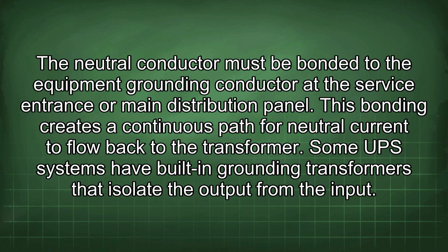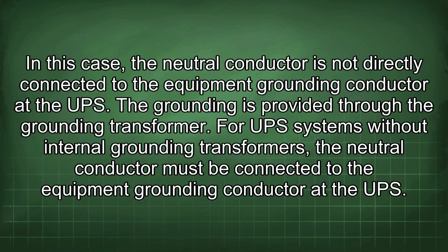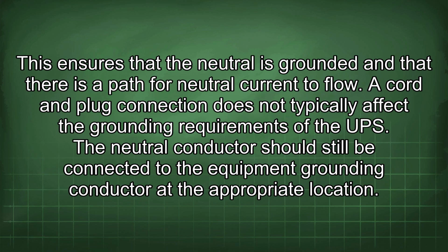Some UPS systems have built-in grounding transformers that isolate the output from the input. In this case, the neutral conductor is not directly connected to the equipment grounding conductor at the UPS. The grounding is provided through the grounding transformer. For UPS systems without internal grounding transformers, the neutral conductor must be connected to the equipment grounding conductor at the UPS. This ensures that the neutral is grounded and that there is a path for neutral current to flow.